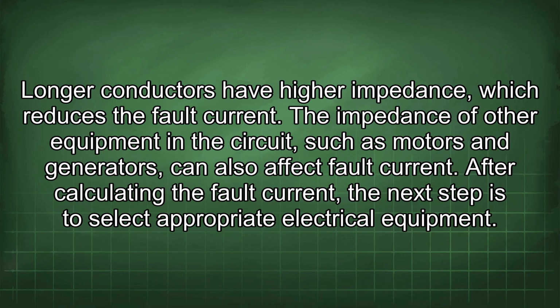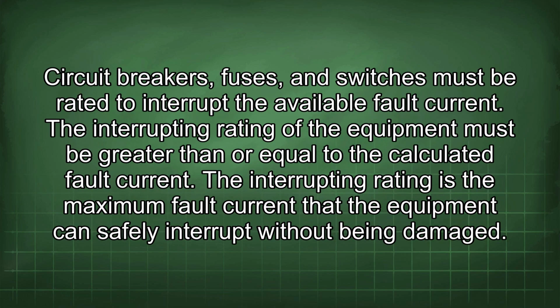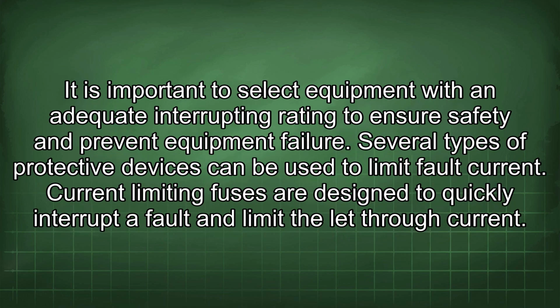After calculating the fault current, the next step is to select appropriate electrical equipment. Circuit breakers, fuses, and switches must be rated to interrupt the available fault current. The interrupting rating of the equipment must be greater than or equal to the calculated fault current. The interrupting rating is the maximum fault current that the equipment can safely interrupt without being damaged. It is important to select equipment with an adequate interrupting rating to ensure safety and prevent equipment failure.